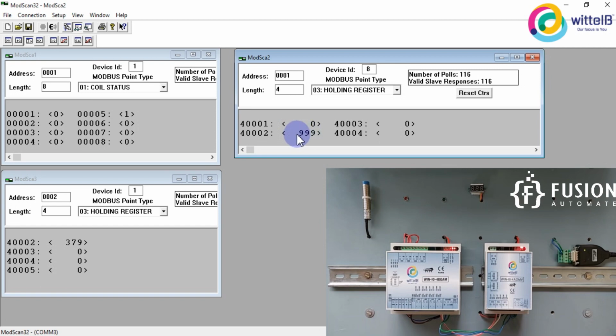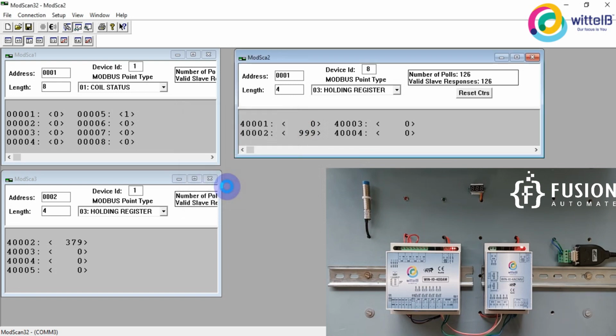If I update the value 0 on this 40,002, then as you already know, my AO2 is connected with the AI1, so this 40,002 is directly connected with that 40,002. I have connected them with this white and red cable. So if I update the value to 0, you will see the change here. You will see the value 0. This is how you can troubleshoot both of your Modbus IO cards.